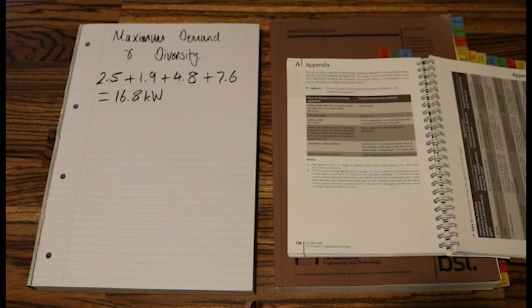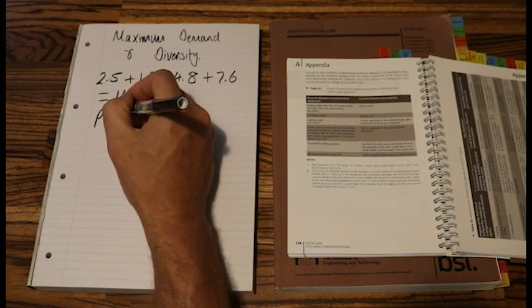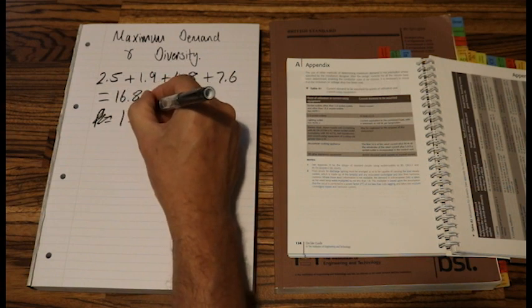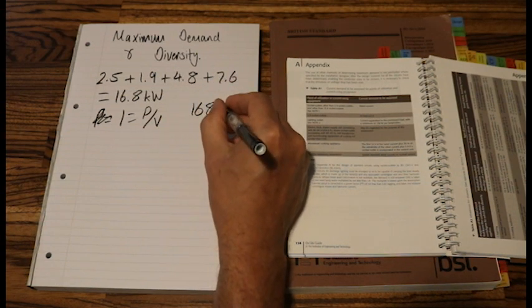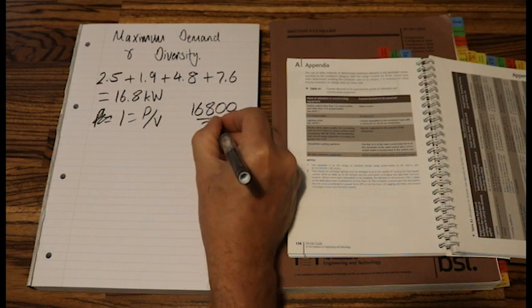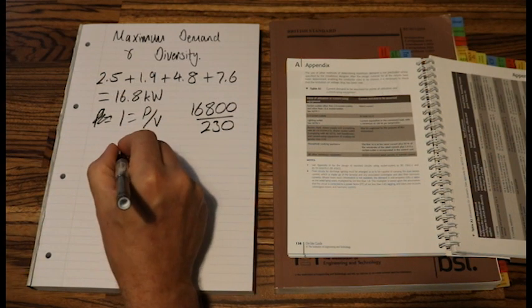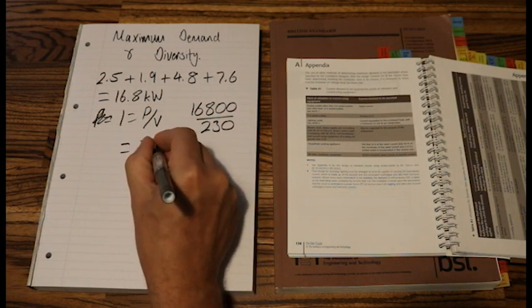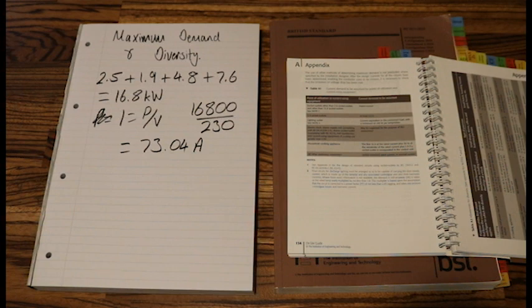Now we need to work out our current. So we'll use our formula of P equals I times V, transpose that, so we do power divide volts equals current. So let's input those numbers. So 16,800 over 230. That is going to equal 73.04 amps. So that's my total current.